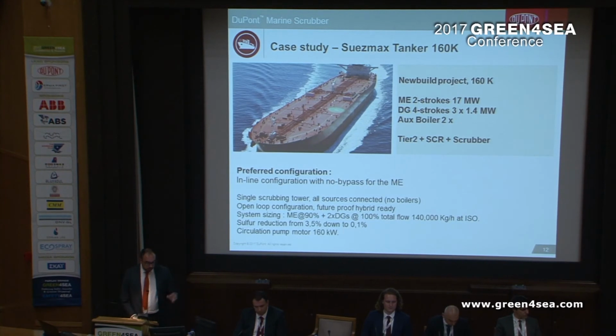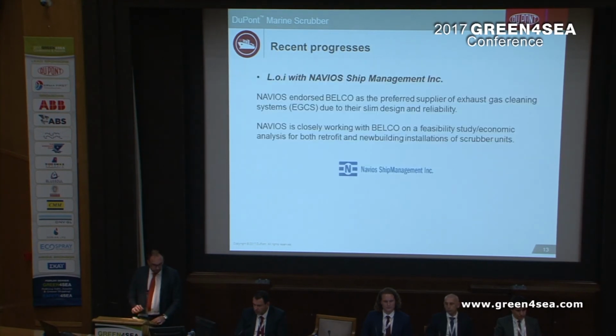So this is a single tower to accommodate everything. The system is sized for the main engine at 90%, two diesel generators at 100%, with a total flow of 140,000 kilos per hour, and a circulation pump motor that required 160 kilowatts.